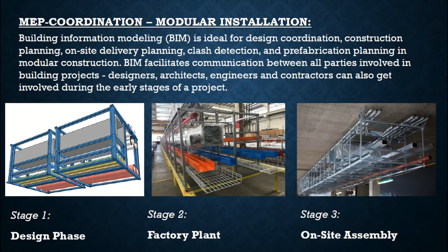In the below images, I have mentioned the three stages of modular installation. Stage 1, design phase; stage 2, factory plant; and stage 3, on-site assembly. Stage 1 is the design phase, in which the building information modeling process is done by using Revit or any other such software. After the design phase is done, the model is transferred to the factory plant, where the services are prefabricated, tested by the respective engineers, and transported to the site. In stage 3, the transported models are assembled on the site in the required locations by the properly coordinated drawings. The models coming from the factory come with a tag, which will enable the sequential installation on-site.